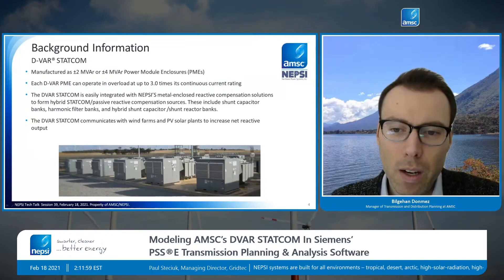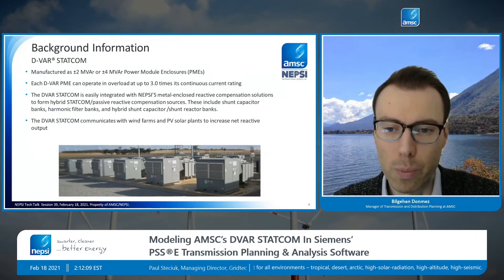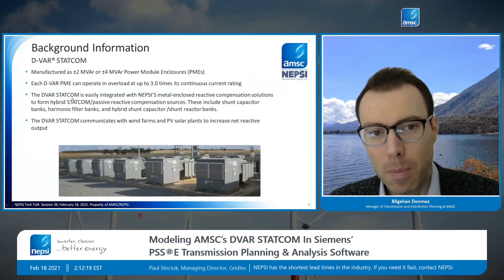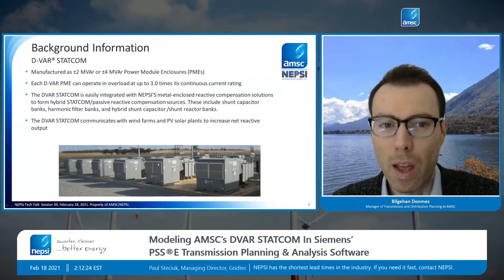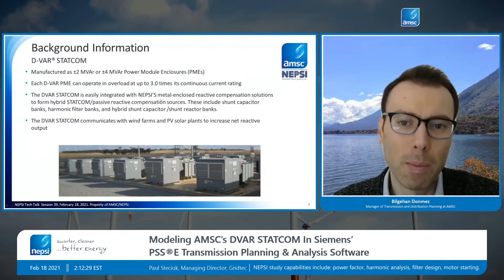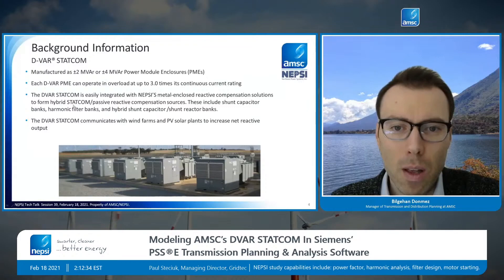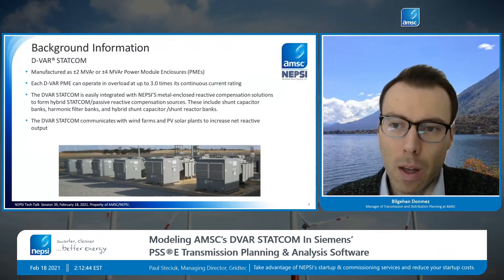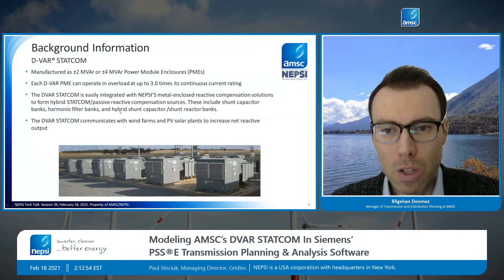These systems include the power module enclosure and a master control enclosure, which sits inside a control room — that's the brains of the overall system. Together, we call that a D-VAR STATCOM system. In addition to the inverters, we can add NEPSI's metal-enclosed reactive compensation solutions to form a hybrid system. The STATCOM will be the first responder, and NEPSI's equipment increases its range, including shunt capacitor banks, harmonic filter banks, or a combination of capacitors and reactors.